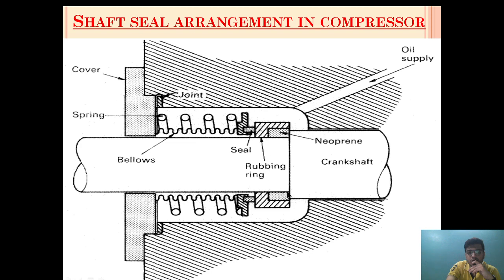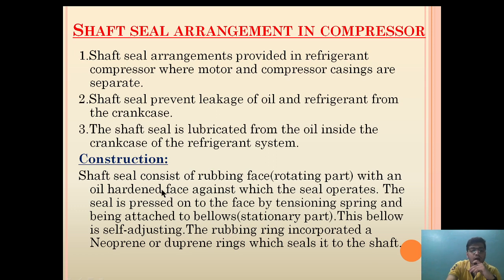This is a neoprene rubber ring. In every seal, there should be two modes of protection: one is parallel and the second is perpendicular. The parallel leakage along the shaft is prevented by the neoprene ring, and the perpendicular leakage is withheld with the help of the sealing arrangement. The shaft seal consists of a rubbing face — the rotating part — with an oil-hardened face against which the seal operates.